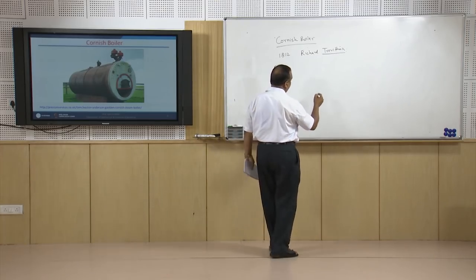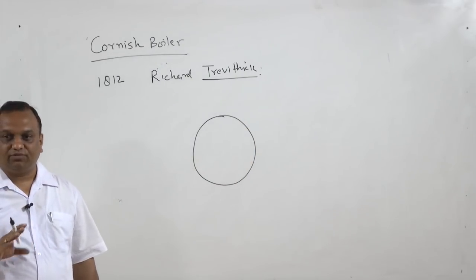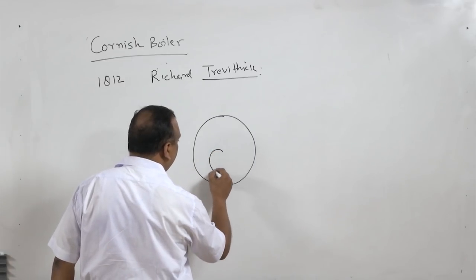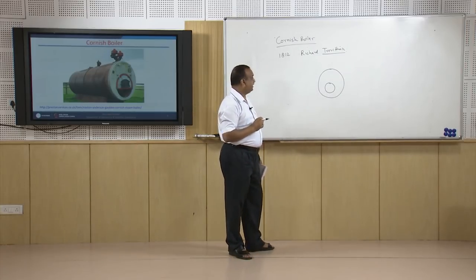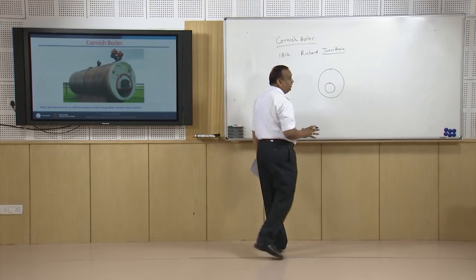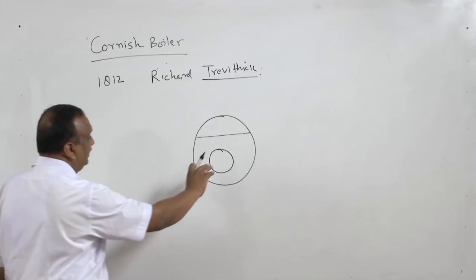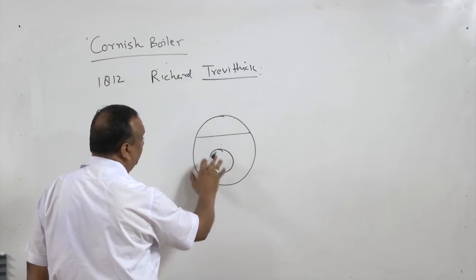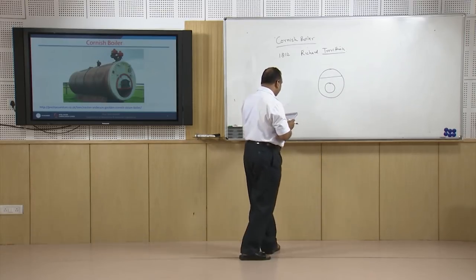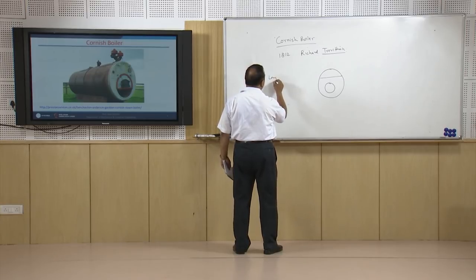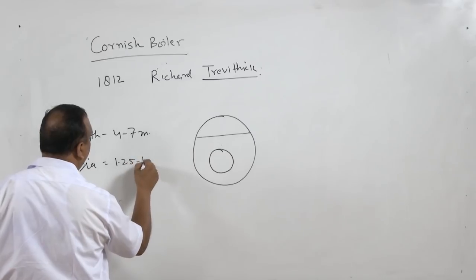In this boiler it is also a fire tube stationary boiler with natural circulation and it has only one fire tube. This one fire tube is not concentrically fixed but is offset from the center. The reason is that the shell is never completely filled with water — some space has to be left for steam — so accordingly this tube is fixed so that it is almost in the middle of the water-filled area. The length of this boiler is 4 to 7 meters and the diameter of the shell is 1.25 to 1.75 meters.